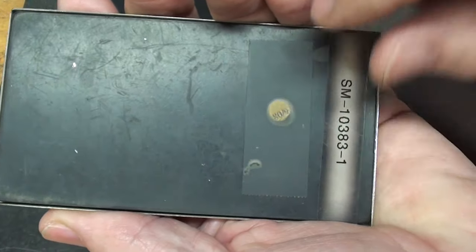I found that extremely interesting and I hope you did as well. There are the final readings again in micro inches on the three samples. Also interesting to note that again this is the finest one. The smaller the number the less roughness, but I can feel on the coarse one with my fingernail I can feel the ridges much more than I can on the other two.